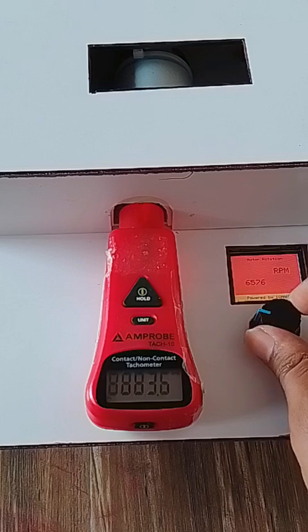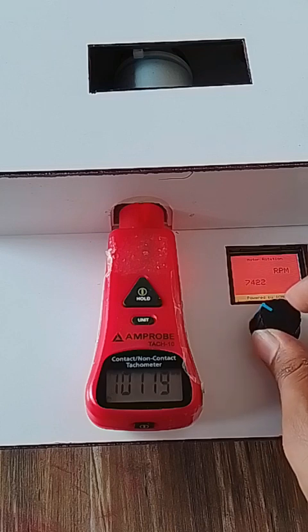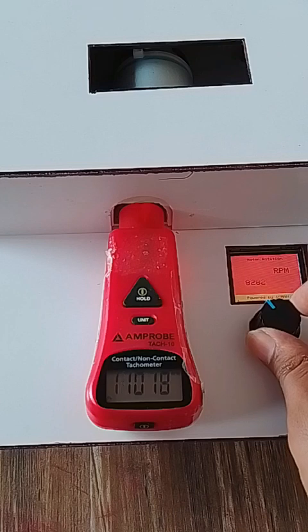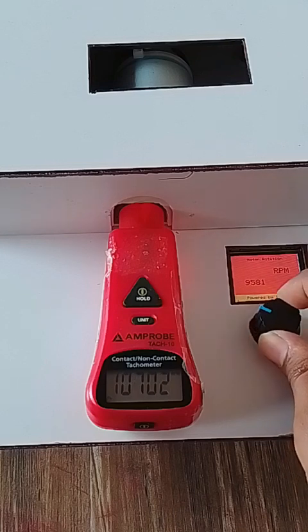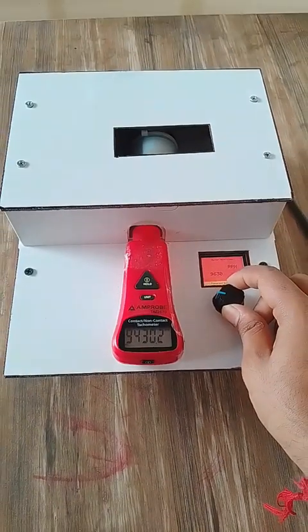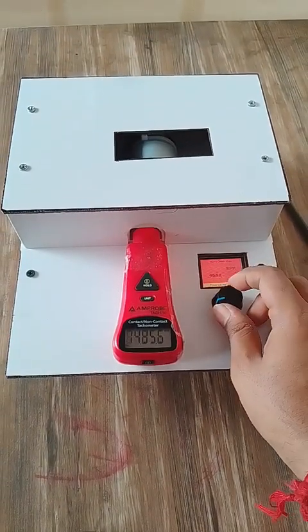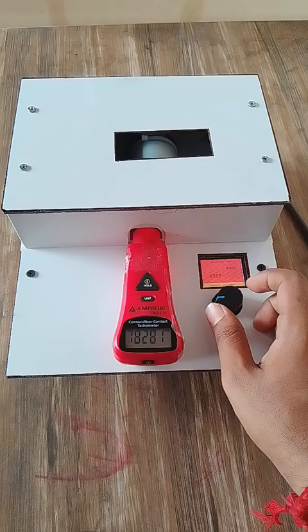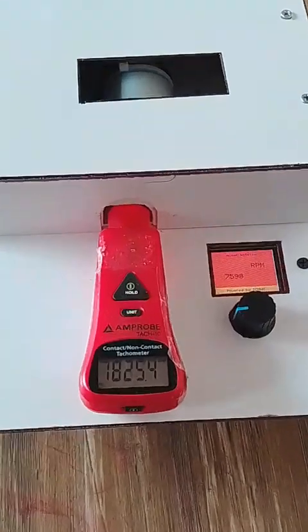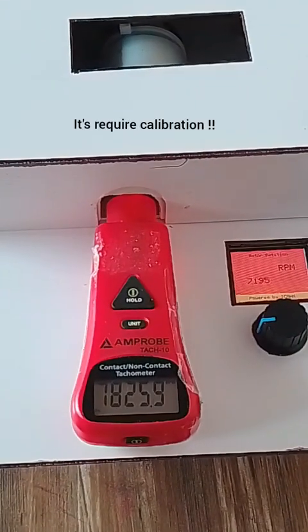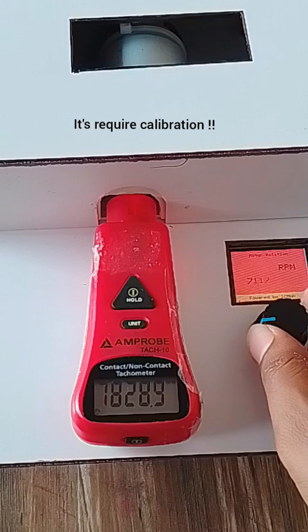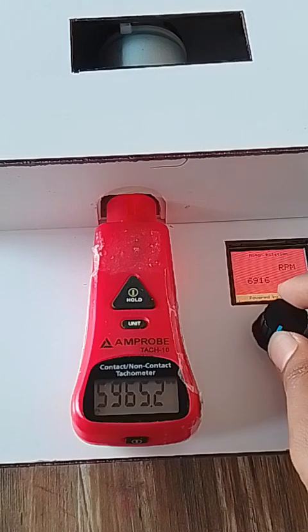I found that there is some error that is not acceptable, so calibration with the actual value is required, and a correction needs to be made in the software. First I noted down the whole range of readings with the standard value and made an Excel list.